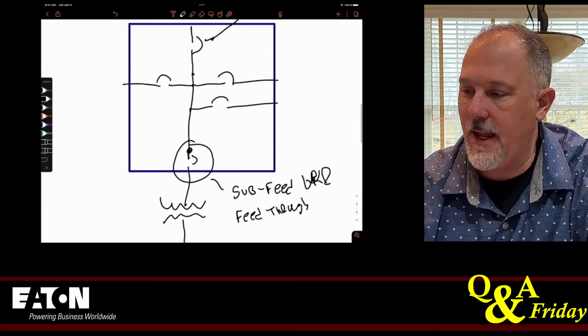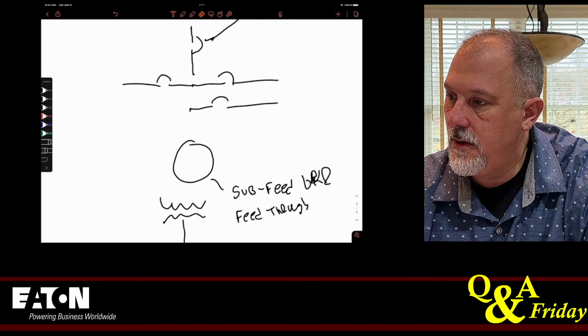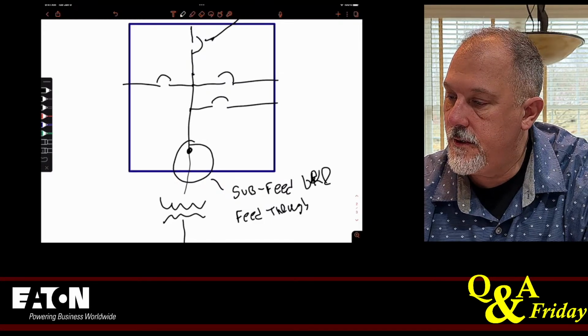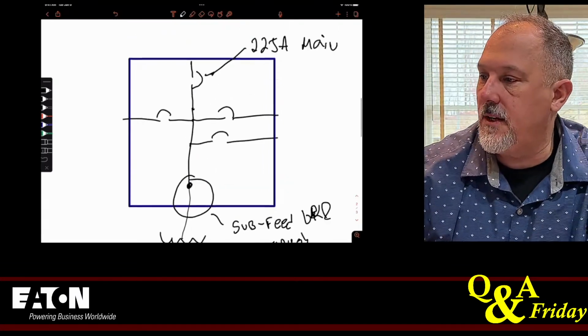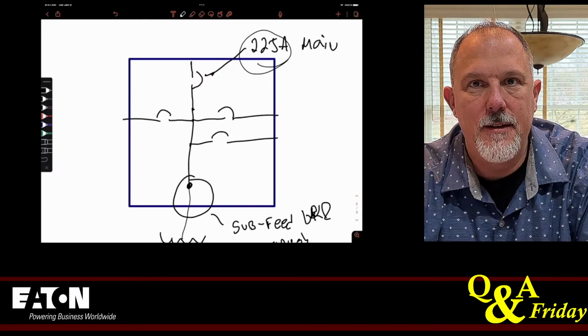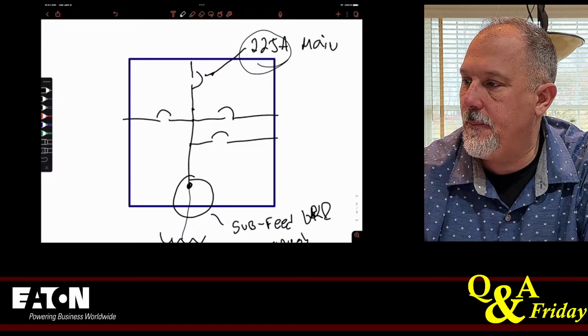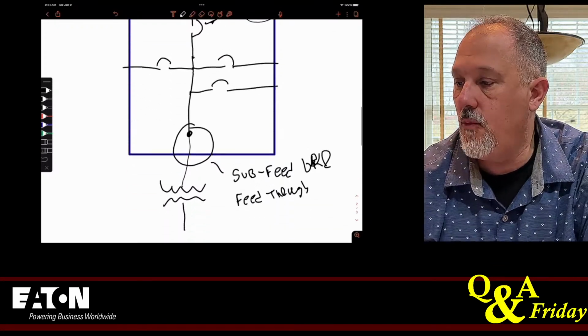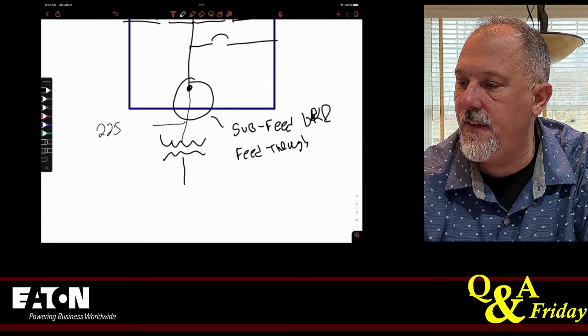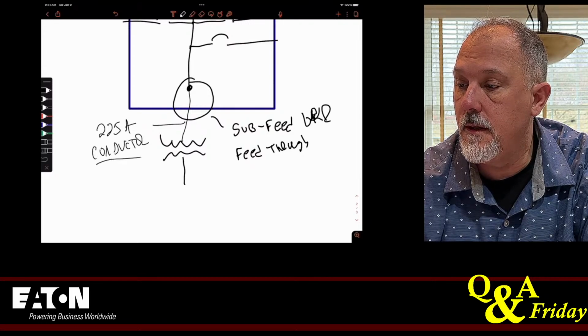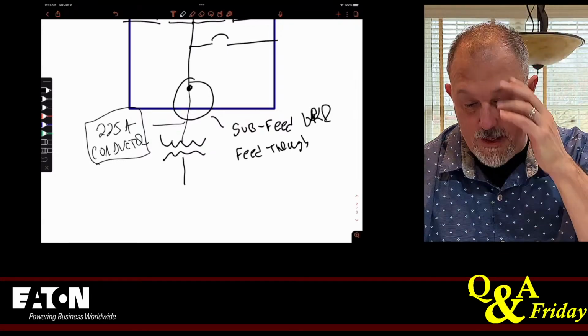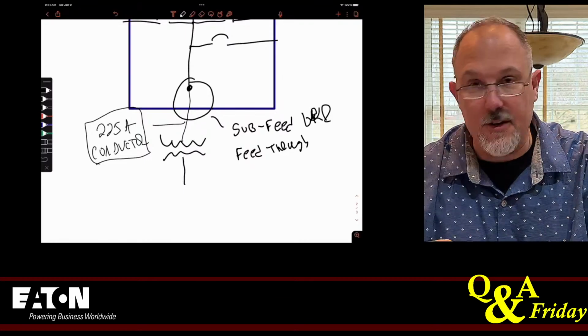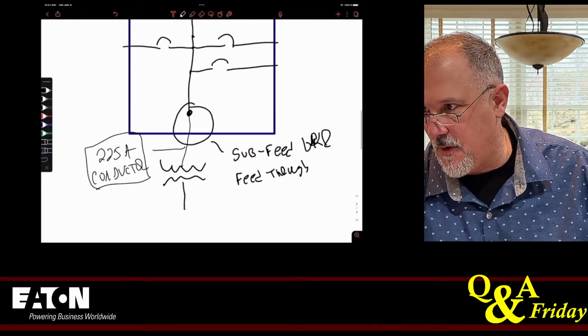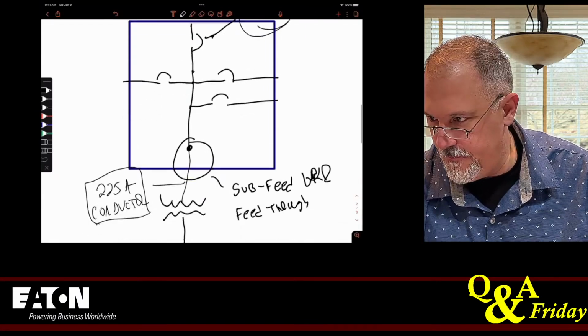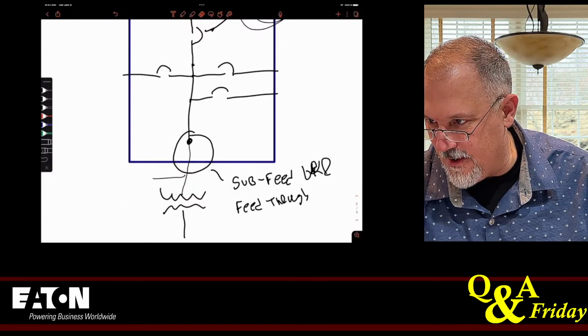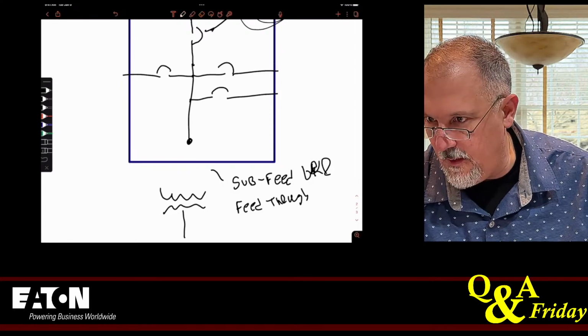If that was a 225 amp main, I could just do that and not put an overcurrent protected device, because this now provides my protection for that transformer. That 225 amp breaker is protecting the panel and all of its loads, of which this is one, as long as that is 225 amps worth of conductor. Now you'd have to weigh that against the other problem: I can't disconnect that transformer without shutting down the old panel. It's probably not a good idea. So let's take that one off the shelf. We came up with the idea and then we threw it away.